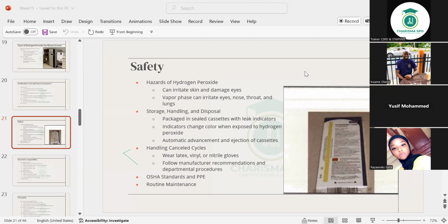Then, when you are handling canceled cycles, at my end we try to make the items dry before we prepare them for the autoclave. If it goes in wet, a lot of times the cycle will fail. If a cycle fails like that with the hydrogen peroxide, you must wear your latex, vinyl, or nitrile gloves, which are readily available at the SPD. But to be safe, we've told you about the PPE. When you go there, it should be 100% PPE all the time until you get out. Your gloves must be there. On the clean side you may need eye shields, but for your own safety, like me, I always have a mask on at the SPD, whether I'm on the clean side or wherever.